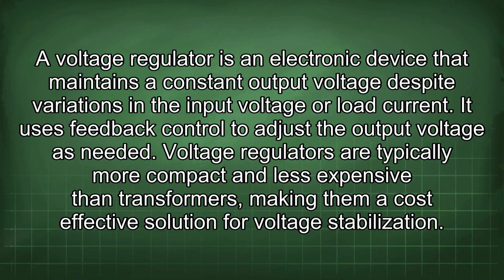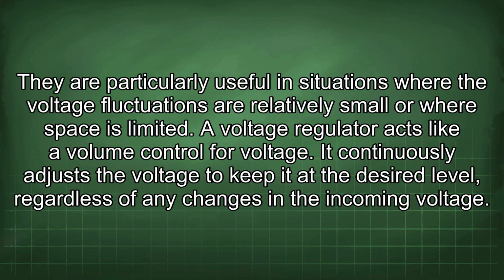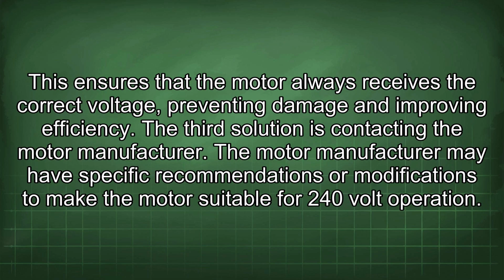Voltage regulators are typically more compact and less expensive than transformers, making them a cost-effective solution for voltage stabilization. They are particularly useful in situations where the voltage fluctuations are relatively small or where space is limited. A voltage regulator acts like a volume control for voltage. It continuously adjusts the voltage to keep it at the desired level, regardless of any changes in the incoming voltage. This ensures that the motor always receives the correct voltage, preventing damage and improving efficiency.